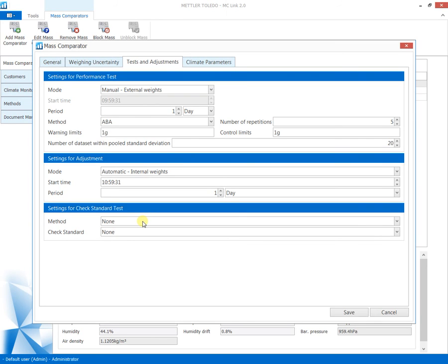To generate statistical data for subsequent uncertainty analysis, check standard test settings are defined. The check standard test is executed according to the needs in the laboratory with the laboratory client.